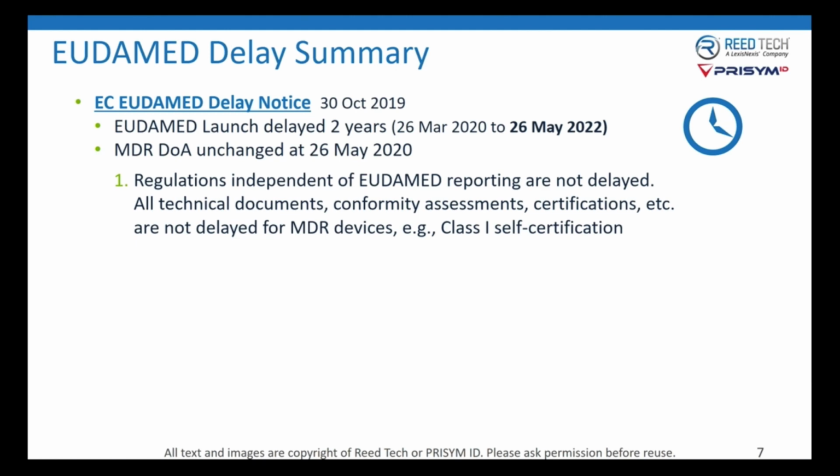So all those activities related to Class 1 self-certification for new MDR products, and those that you'd like to conduct after the date of application, all are still in force, and you should be well on your way with engaging notified bodies for some of your other classes. That is not at all delayed.